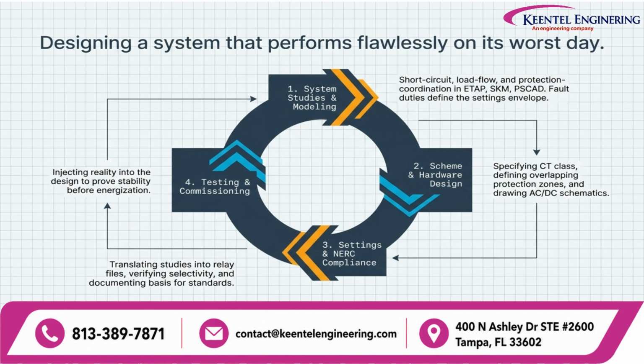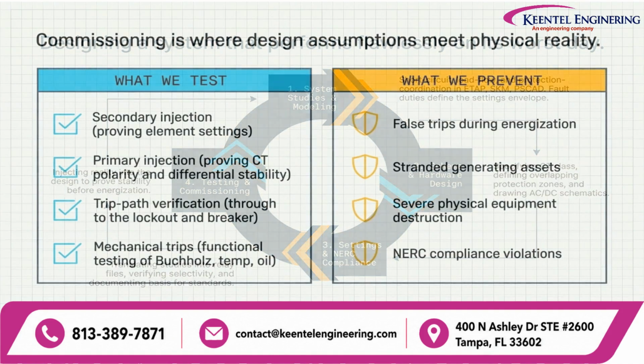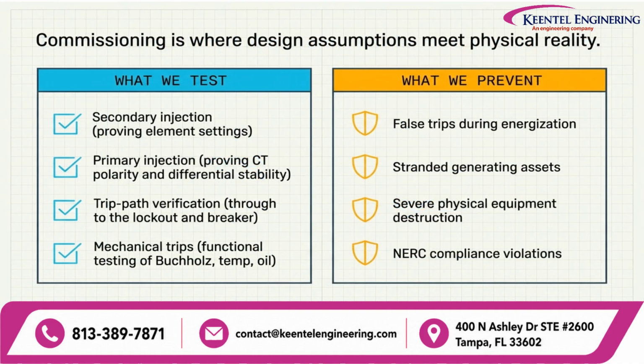The objective is to inject real electrical conditions into the protection system and prove that the design behaves as intended before energization. This creates a closed engineering loop. Study the system, design the protection, configure the settings, test the actual hardware, then verify that reality matches the engineering model. Commissioning is where engineering assumptions meet physical reality.